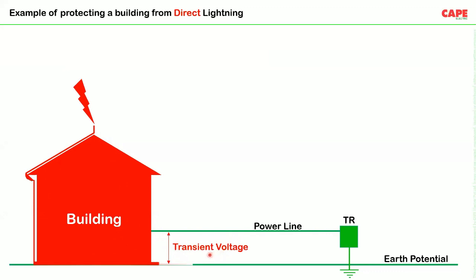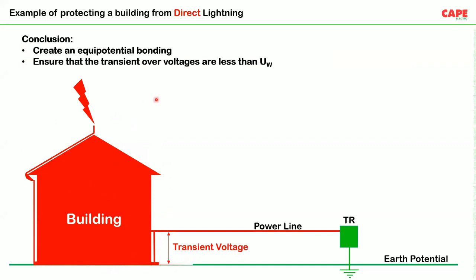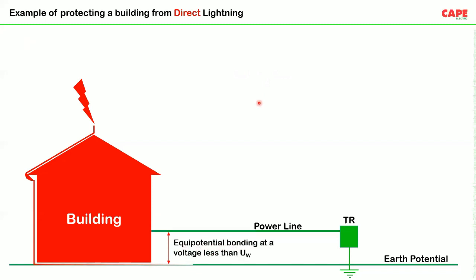So what do we do? We connect SPDs at the mains incoming panel. You install an SPD here. This is an SPD, and the SPD is creating equipotential bonding between the earthing and the connected line. As a result, the line which is circulating inside our building has the same potential as the earth. So a perfect equipotential bonding is created. As a result, all the equipment inside our building are now safe. Now, once you make equipotential bonding with an SPD, the most important parameter we should understand is called UW, the voltage impulse withstanding capacity of your equipment, of your connected load.